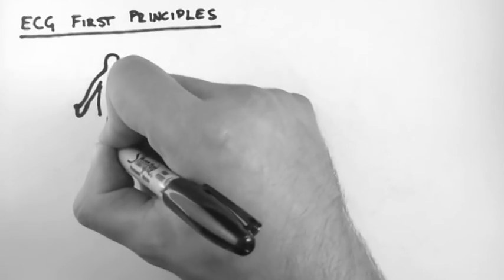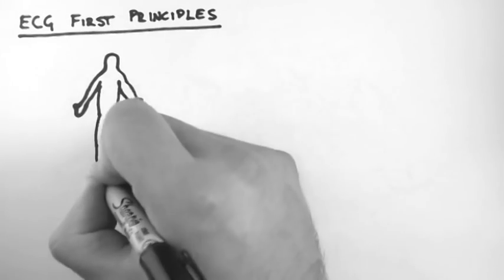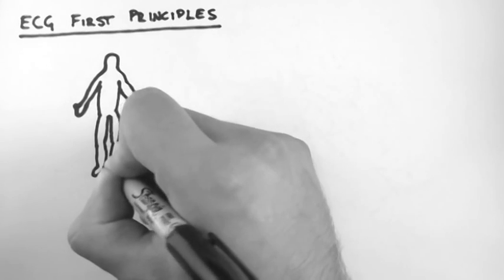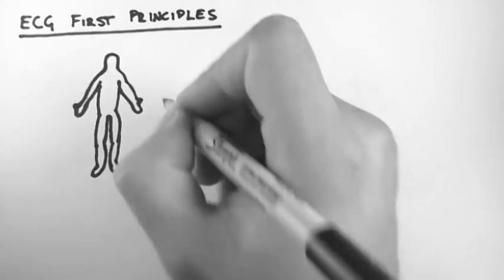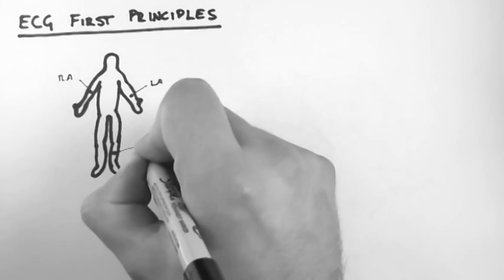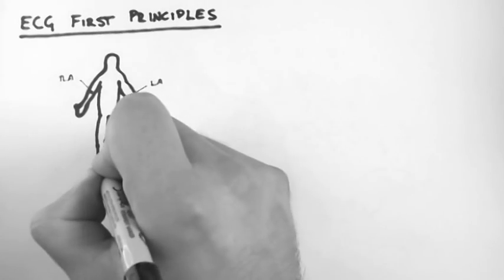So first of all we're going to look at where you attach the leads of an ECG machine to a patient. First of all, there are four leads which are attached to the limbs of a patient. These are abbreviated LA for left arm, RA for right arm, LL for left leg and RL for right leg.